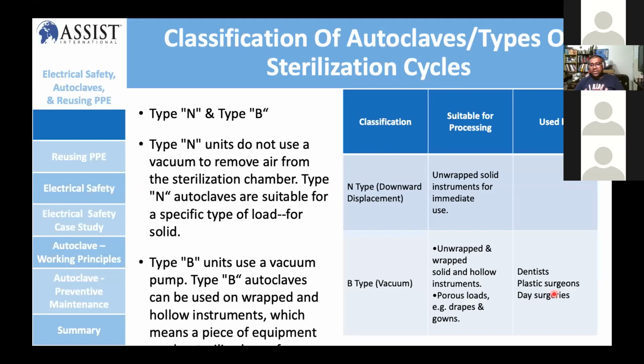Okay, classification of autoclaves and types of sterilization cycles. Normally you're going to see that in hospitals, type N and type B are very common. A type N unit does not use vacuum to remove the air. Type N is for unwrapped solid instruments for immediate use. These are downward displacement or gravity types. These are suitable processes. Normally you use unwrapped items, solid instruments, all that, which you want to use immediately. And type B is the vacuum type. So you can use it on wrapped and hollow instruments, which means a piece of a load, drapes, gowns, even ventilated tubing, all that. You can even use it in dentistry, plastic surgery and day surgery, all that. So these are the two types that you would normally see in hospitals.